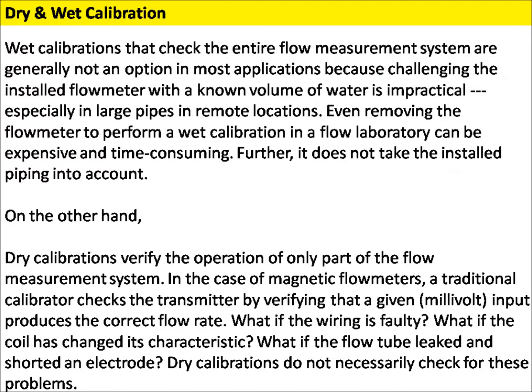Wet calibrations that check the entire flow measurement system are generally not an option in most applications because challenging the installed flow meter with a known volume of water is impractical, especially in large pipes in remote locations. Even removing the flow meter to perform a wet calibration in a flow laboratory can be expensive and time-consuming. Further, it does not take the installed piping into account.